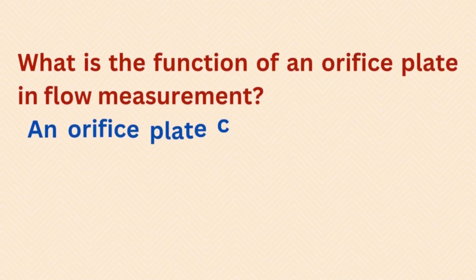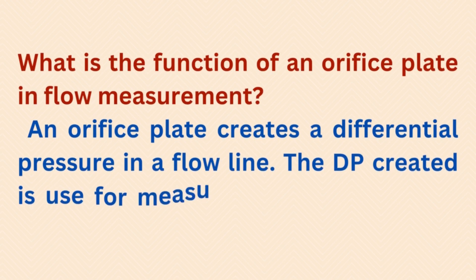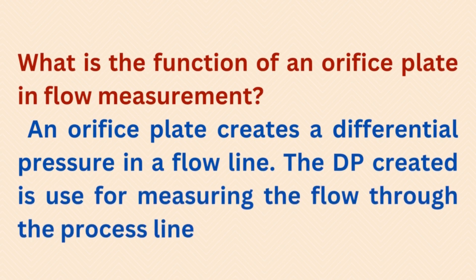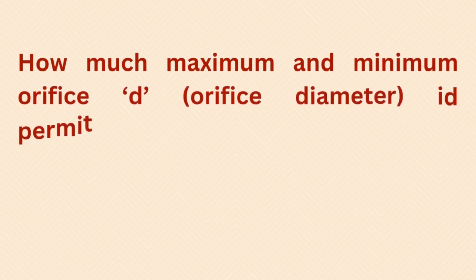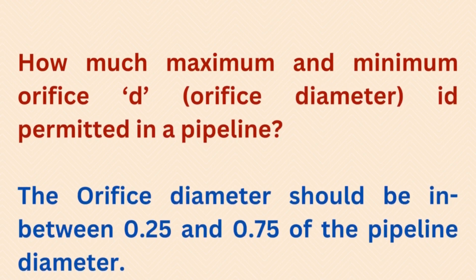What is the function of an orifice plate in flow measurement? An orifice plate creates a differential pressure in a flow line; the DP created is used for measuring the flow through the process line. The orifice diameter should be between 0.25 and 0.75 of the pipeline diameter.